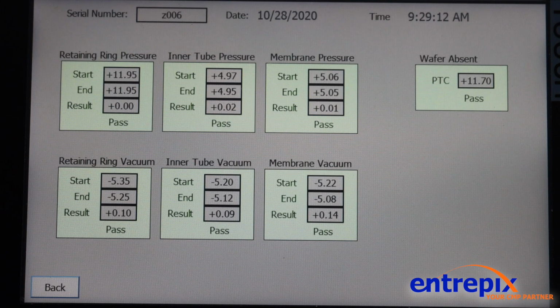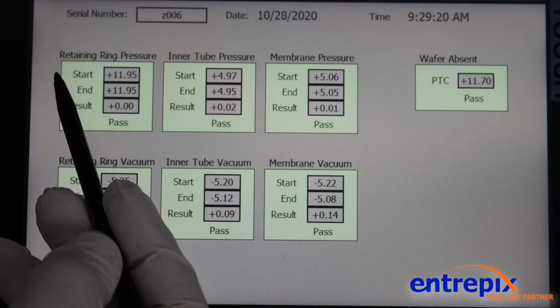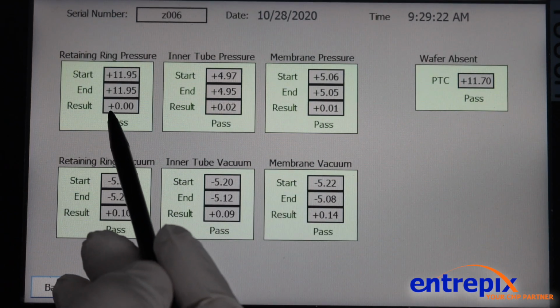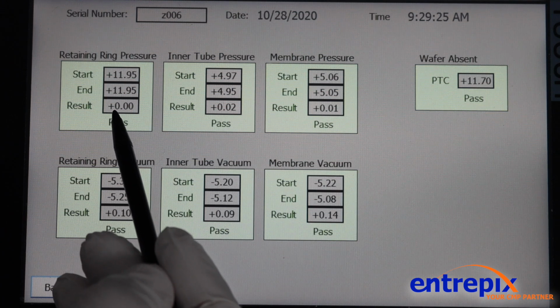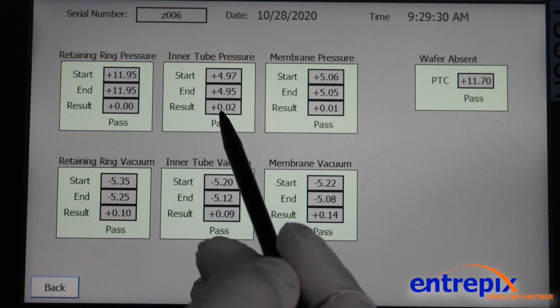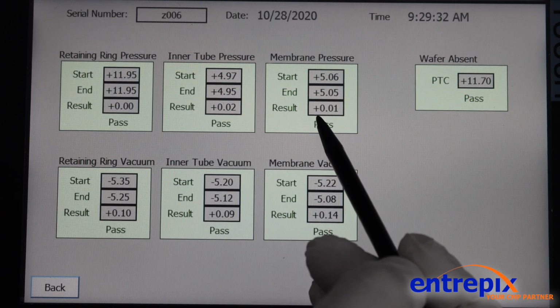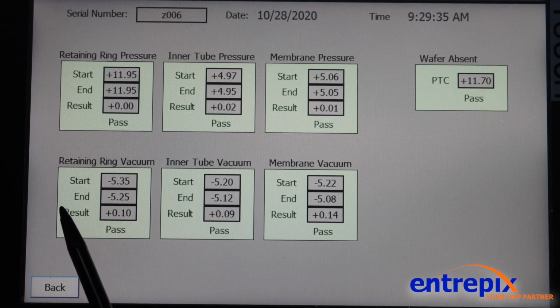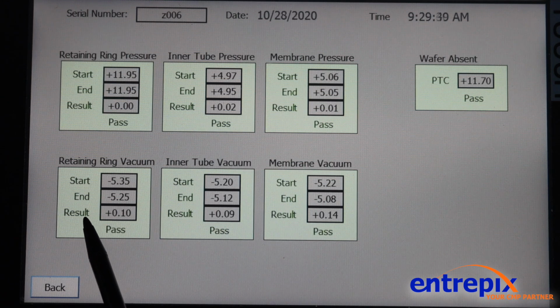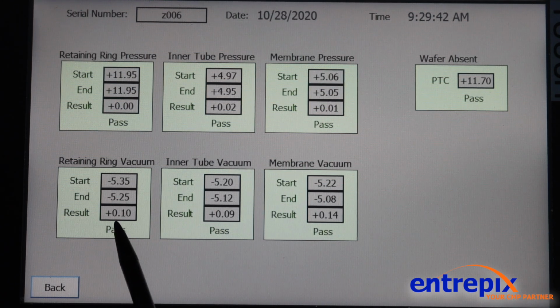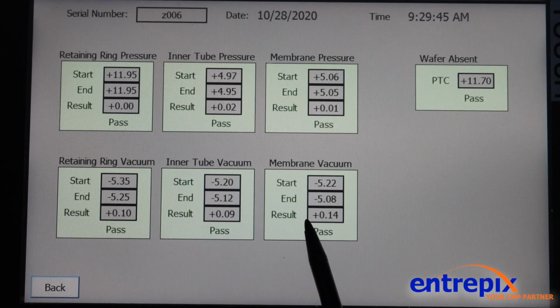Upon completion of the testing, the data screen will display the passing results with a green backer. As you can see, for the pressure testing, we were within the 0.1 requirement of delta over the 30 seconds, with no leak indicated on the retaining ring, a 0.02 on the inner tube, and 0.01 on the membrane. The vacuum side also is indicated here with a passing requirement of 0.5 or better. We easily pass with a 0.1, 0.09, and a 0.14 leak delta.